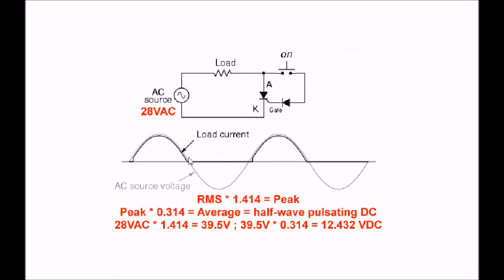Why did I read around 12.5 volts DC? This is why. RMS times 1.414 equals peak. Peak times 0.314 equals average, which equals the half-wave pulsating DC that I got. 28 volts AC times 1.414 is about 39.5 volts. That gives me the peak. 39.5 volts times 0.314 equals around 12.5 volts DC. That's why you saw the voltage we were measuring. And that tells me that the circuit was working.